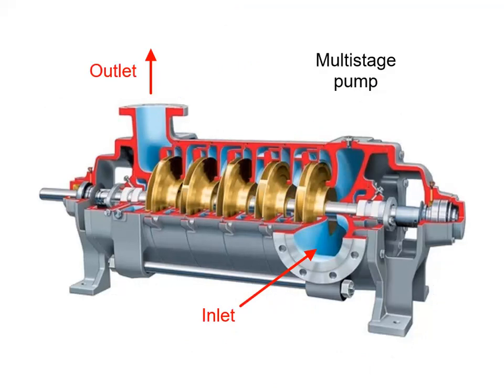Centrifugal pumps can be single-stage or multi-stage. In a multi-stage pump, several impellers are attached to the same shaft. The flow exiting the first stage goes into the eye of the second stage, and the flow exiting the second stage goes into the eye of the third stage, and so on. A multi-stage pump is similar to several single-stage pumps connected in series. It is used to generate a high pressure difference, in other words, a high total pump head.